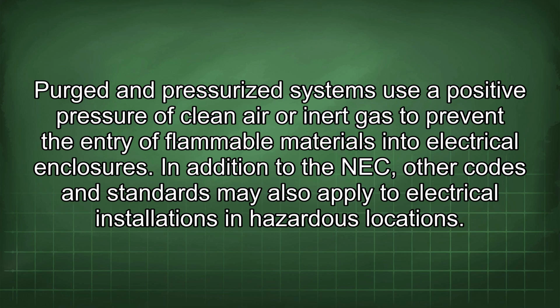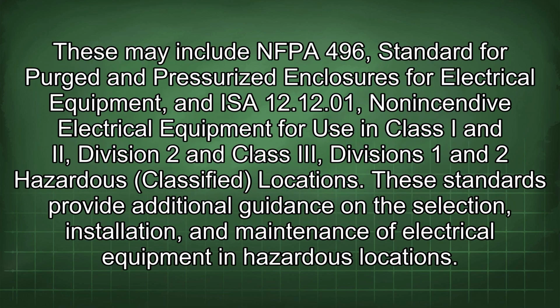In addition to the NEC, other codes and standards may also apply to electrical installations in hazardous locations. These may include NFPA 496, Standard for Purged and Pressurized Enclosures for Electrical Equipment, and ISA 12.12.01, Nonincendive Electrical Equipment for Use in Class I and II, Division 2 and Class III, Divisions 1 and 2 Hazardous Classified Locations. These standards provide additional guidance on the selection, installation, and maintenance of electrical equipment in hazardous locations.